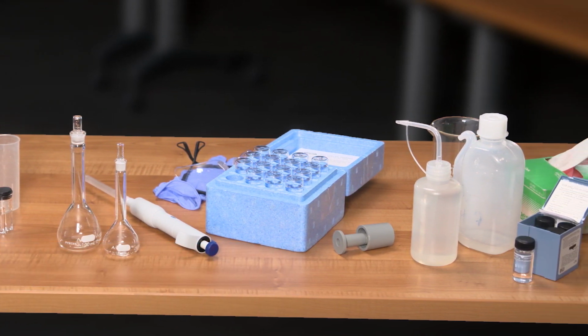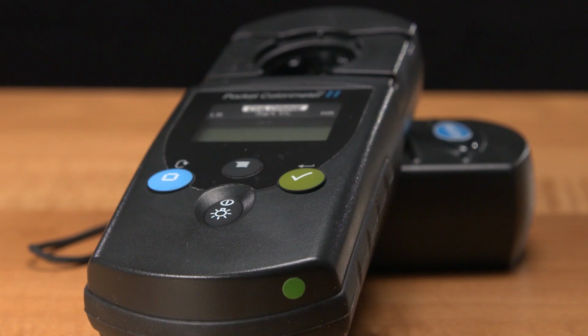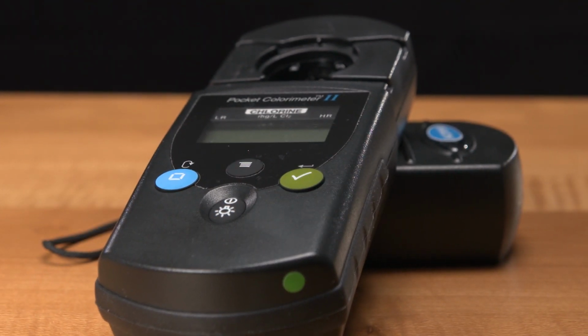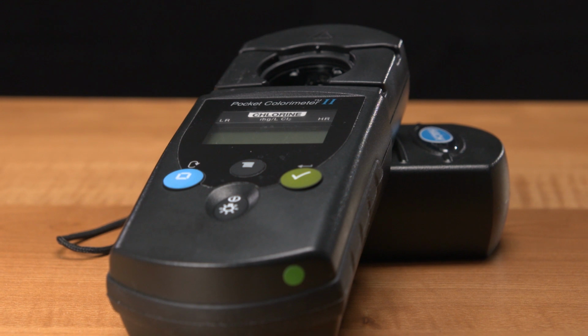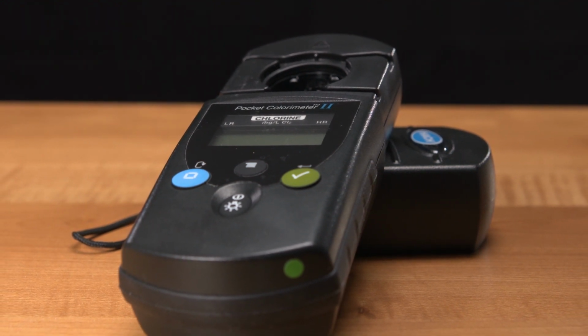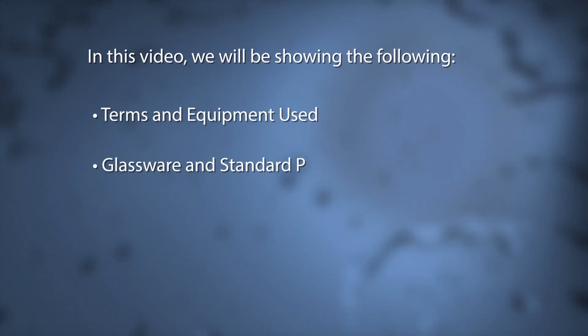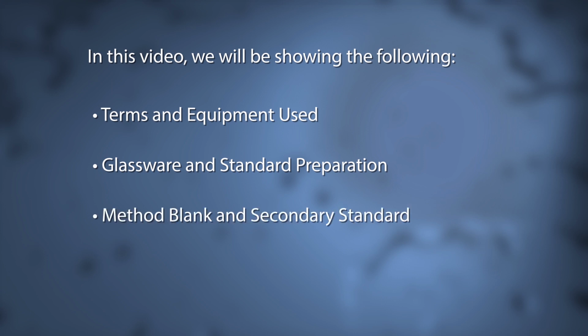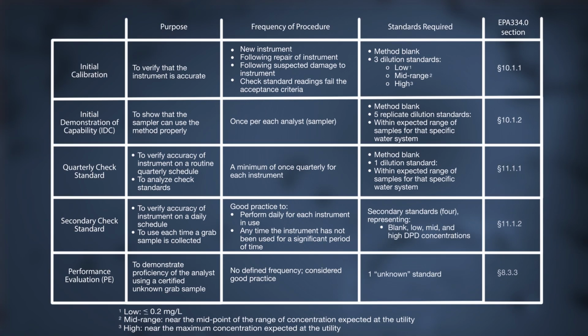To ensure accurate measurements of field grab samples, we must check the performance of the instrument, the quality of the reagents, the cleanliness of the labware, and the skill and consistency of the sample collector. In this video, we will be showing the following: terms and equipment used, glassware and standard preparation, method blank and secondary standard, initial and routine instrument verification. This table summarizes the purpose, procedure frequency, and standards required for verifying your chlorine meter, and defines some of the terms that will be used in this video.